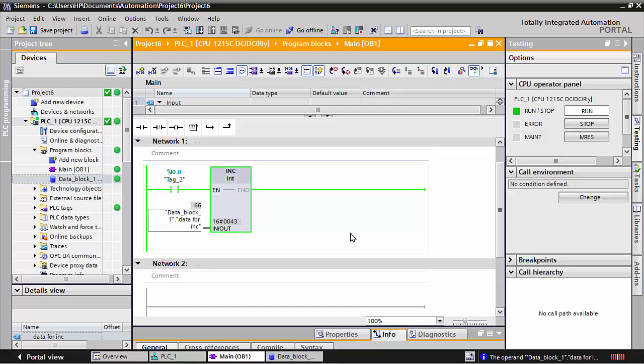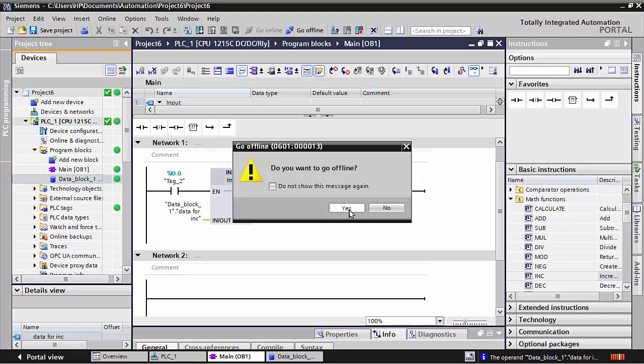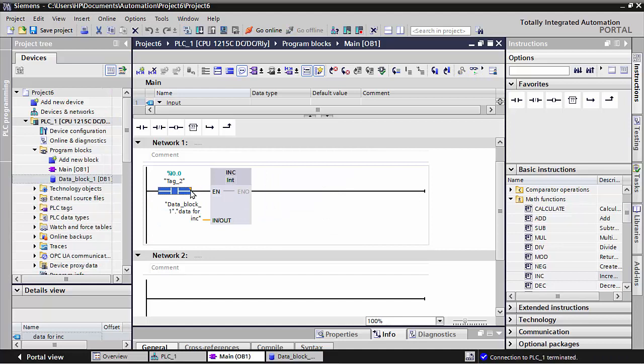See, I give one signal, and after that many counts happen in the increment command, because I am using the direct signal from the hardware. But this is the command and how to use it. You have to choose it here first, and also we use the positive edge. Positive edge means when any signal comes from hardware, from a proximity or a sensor, it must count 1, not 2, however many signals come from outside.